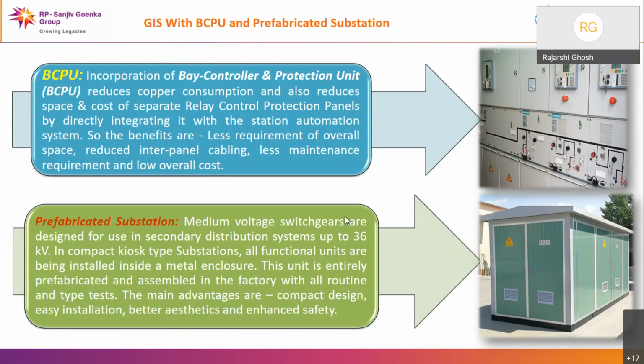the station automation system. You can see in this switchboard, here we have the bay controller units fitted on the switch panel itself. So there is no need to have a separate relay panel, no requirement of additional space. So there is less requirement of overall space, reduced interpanel cabling, less maintenance requirement, and overall low cost. So this is a very smart system which has come in the last few years.